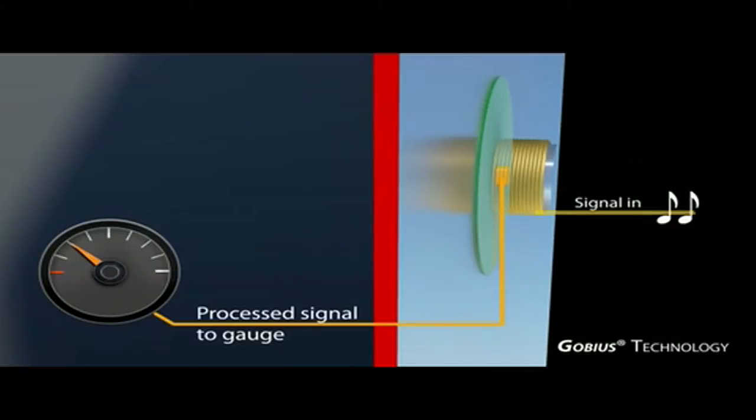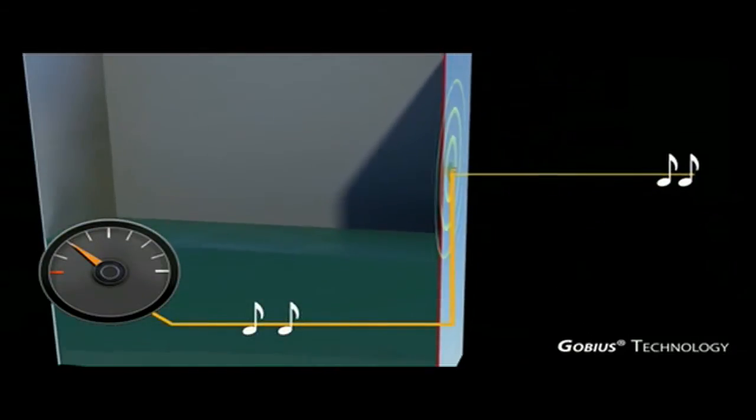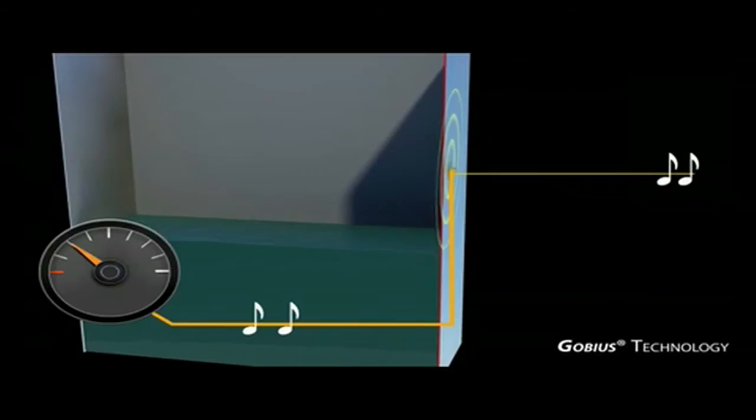The technology's uniqueness is that it measures with a vibration. A small shaker and a small accelerometer cooperate in vibrating and measuring. The tank level can then be determined.